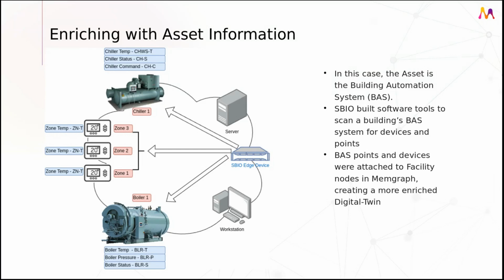This is a very simplified example. Normally, a chiller could have hundreds of points available, a boiler could have hundreds of points, and thermostats on the wall could have tens of points each. So SBIO built software that would go out and scan these pieces of equipment for their points and develop an internal graph database of what this building looked like.